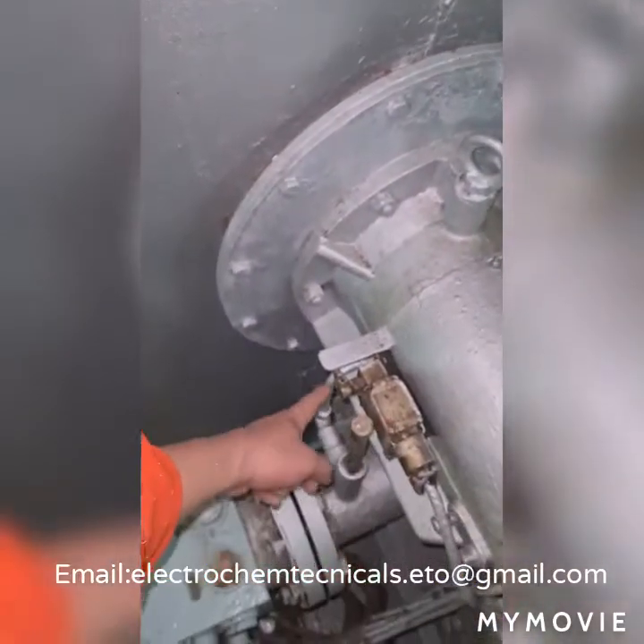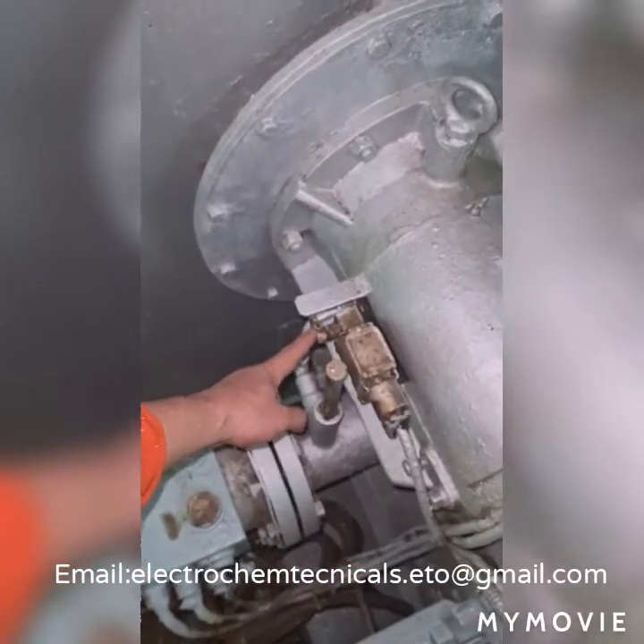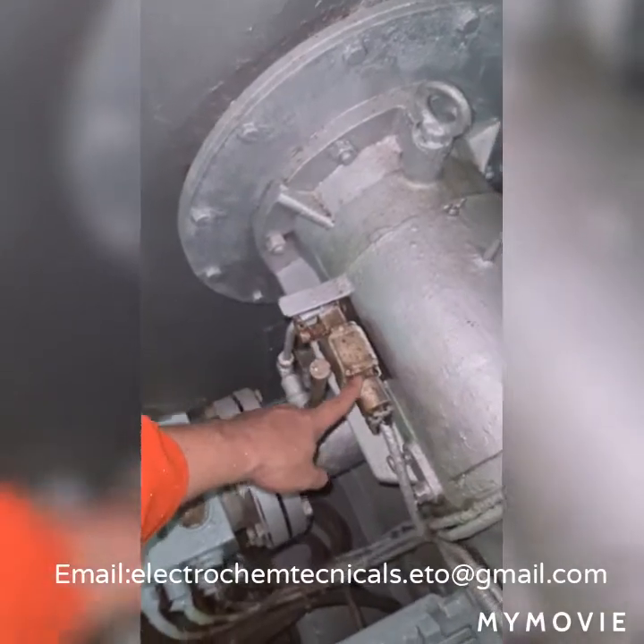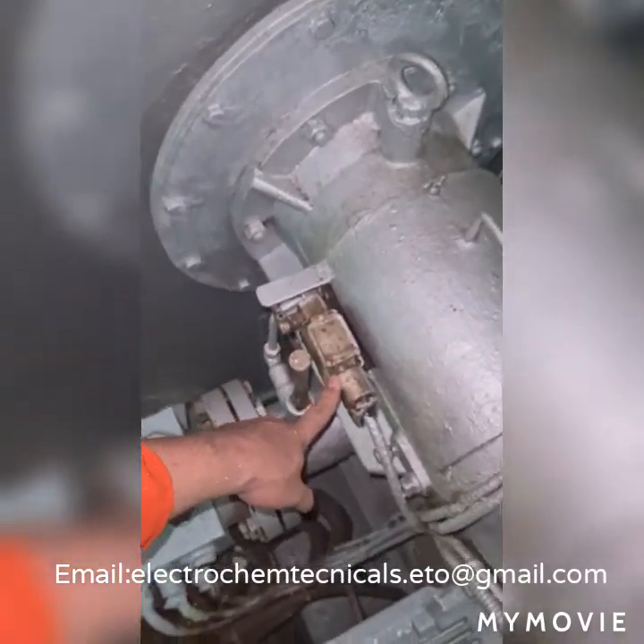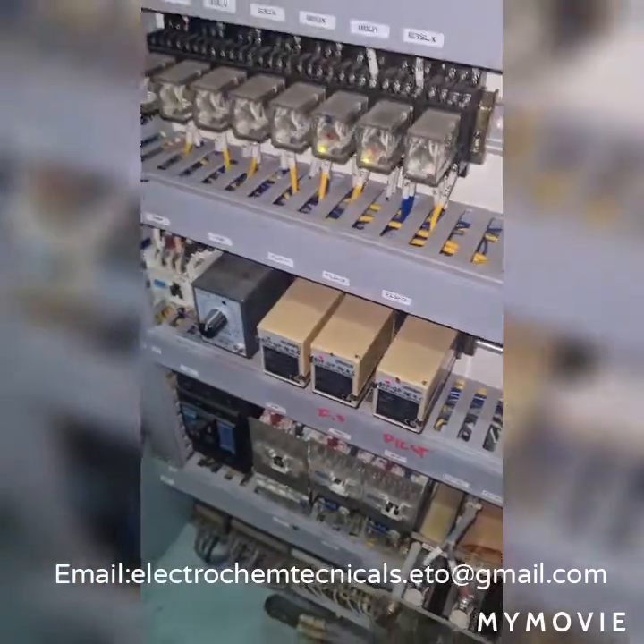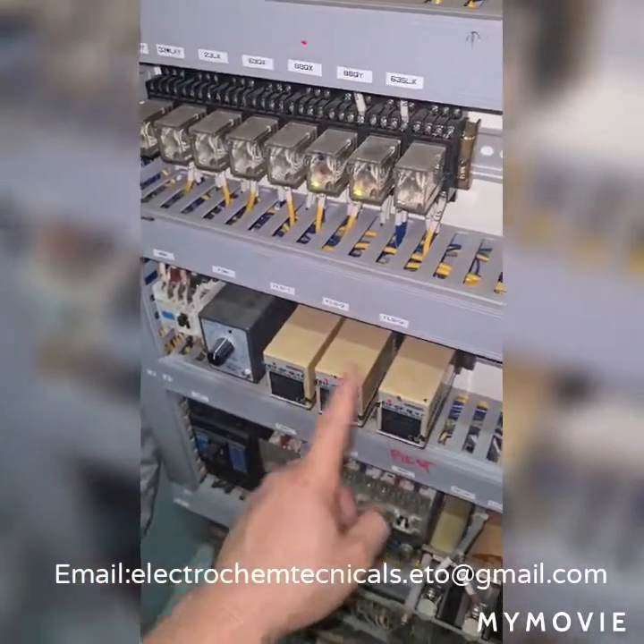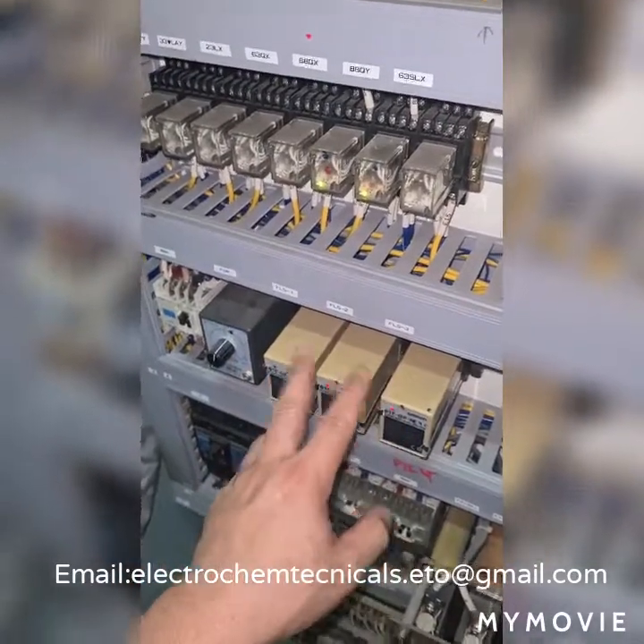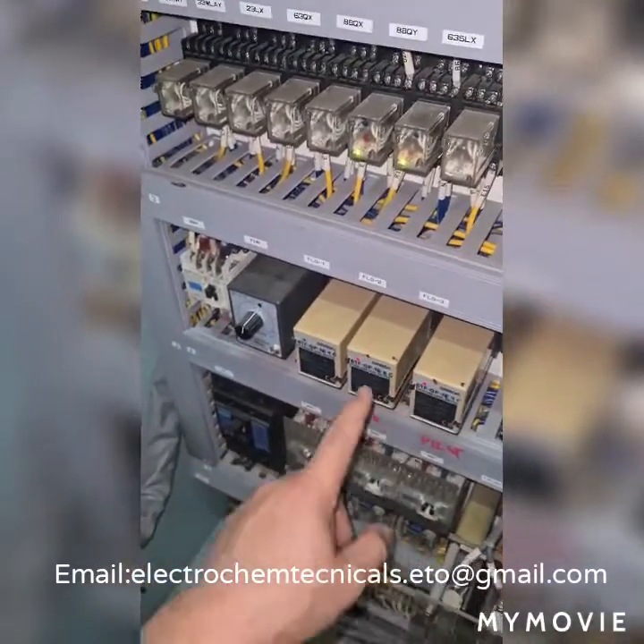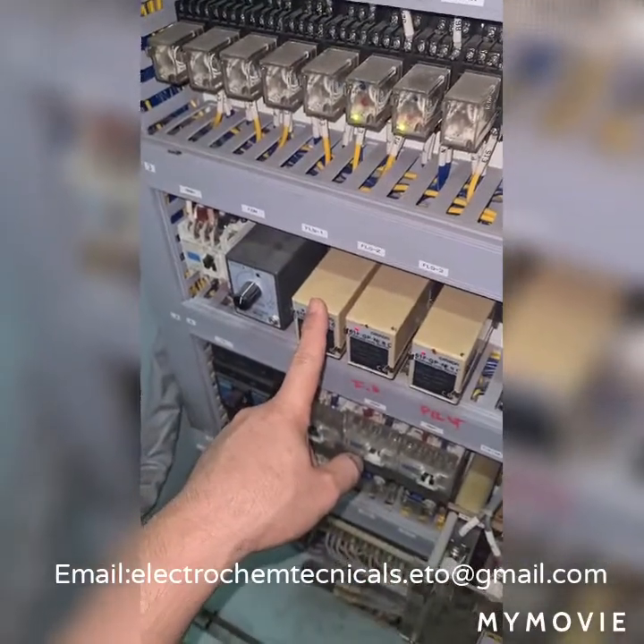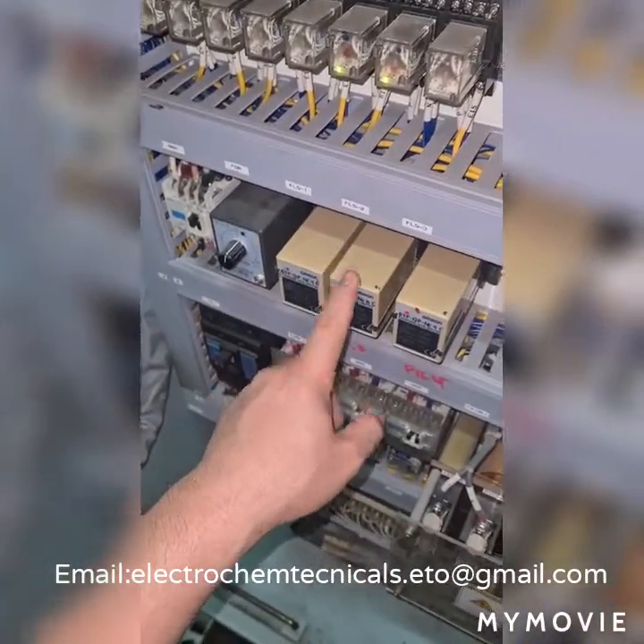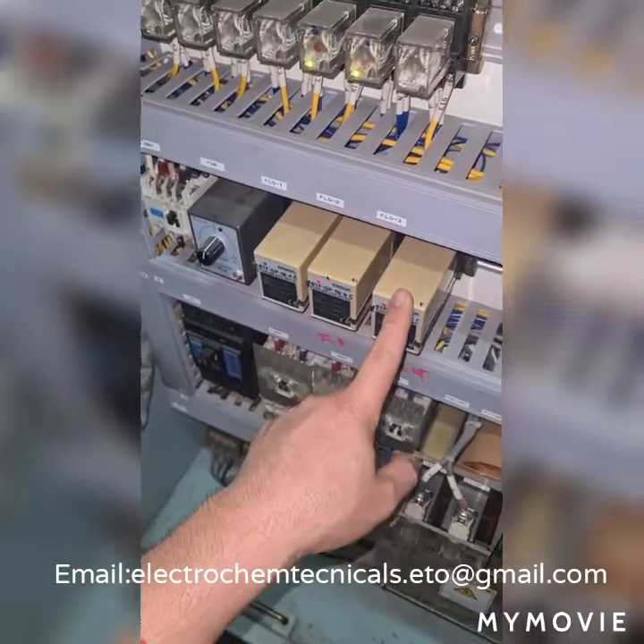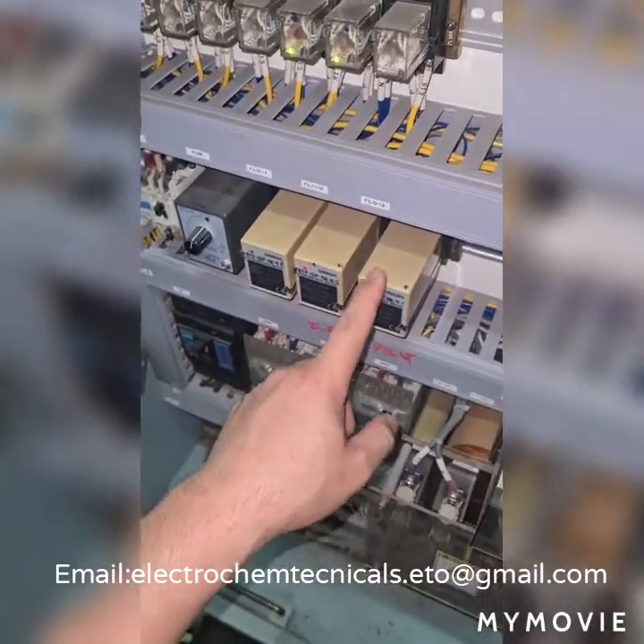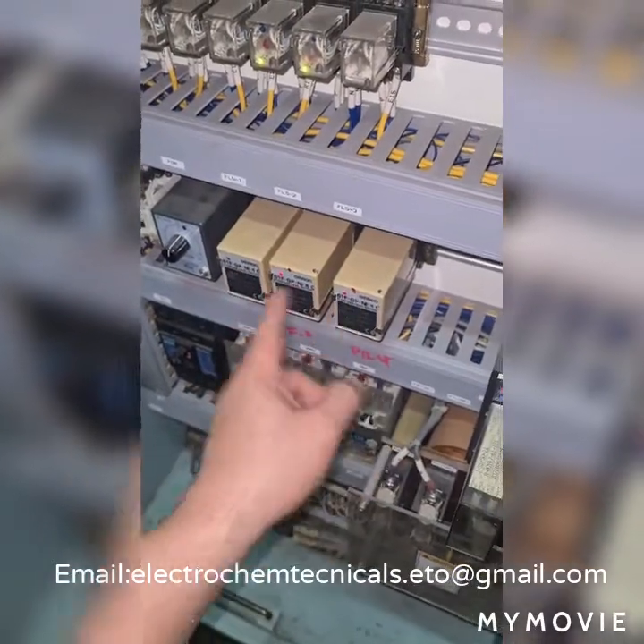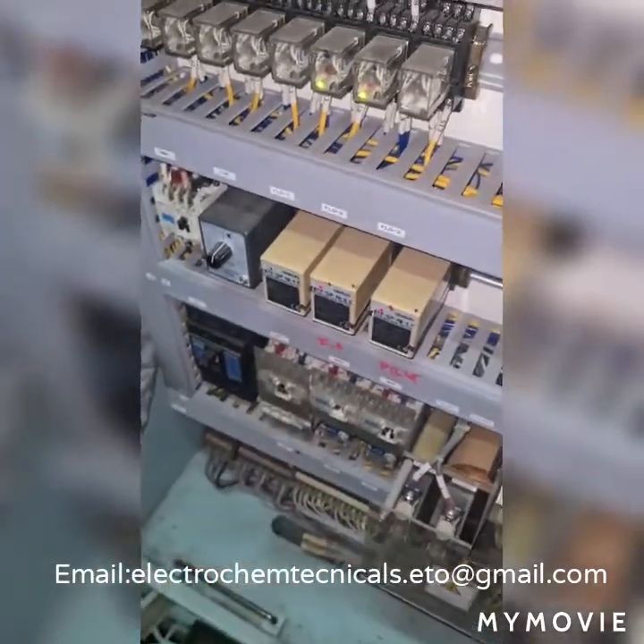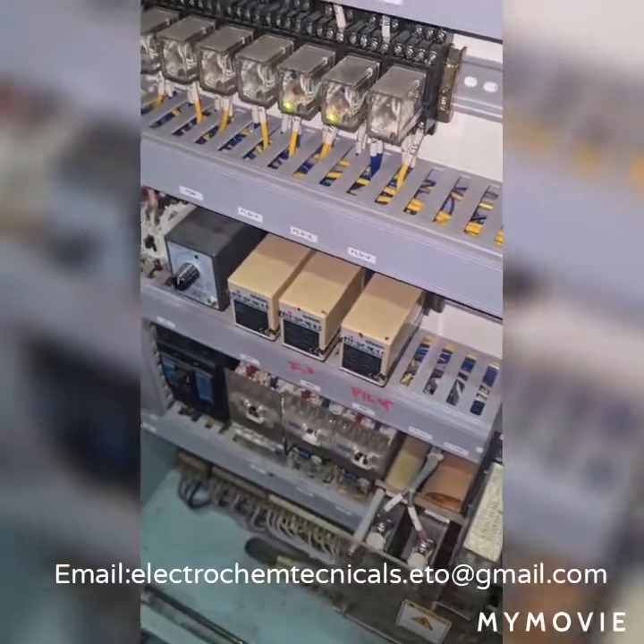This is a limit switch. When this moves up, the maintenance cover alarm will be activated. This is the floatless water level sensor from which the water level of the drum is being monitored. FLS1 for the highest water level, FLS2 for the lowest water level, and number 3 is the low water level cutoff alarm. This is 24-hour monitoring of the water level in the boiler drum.